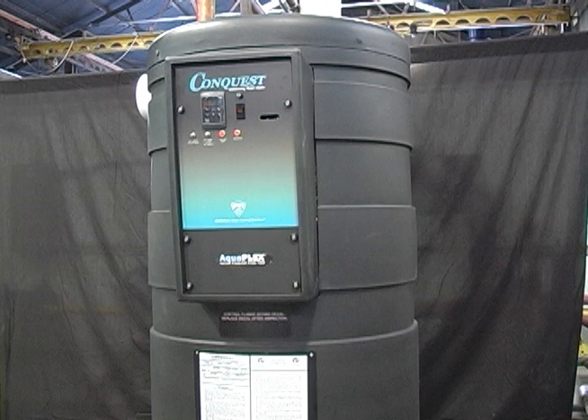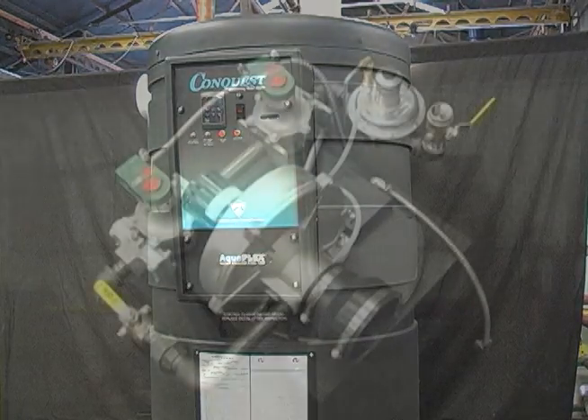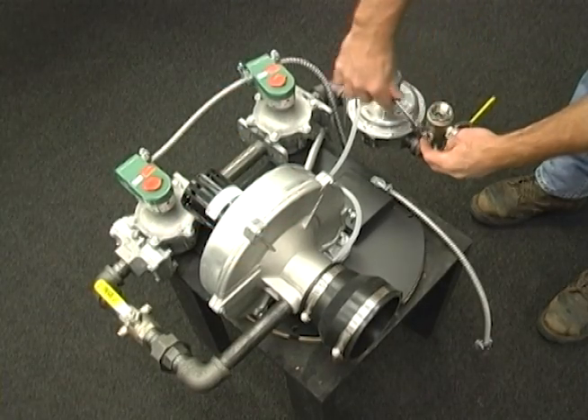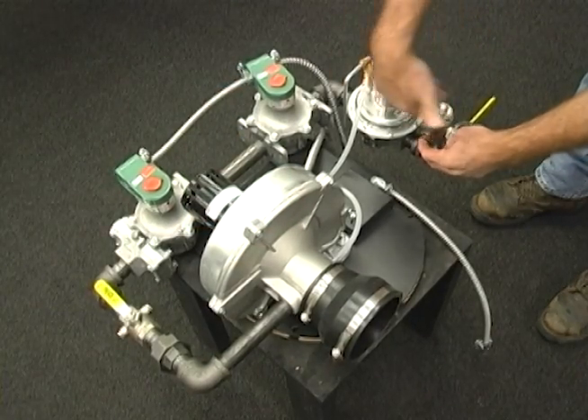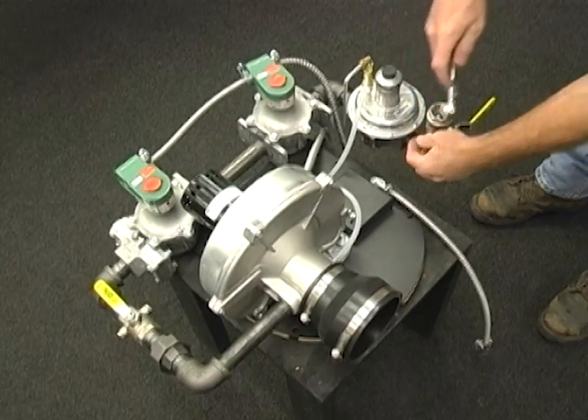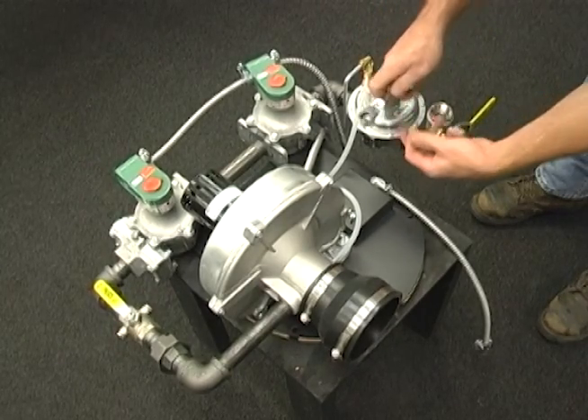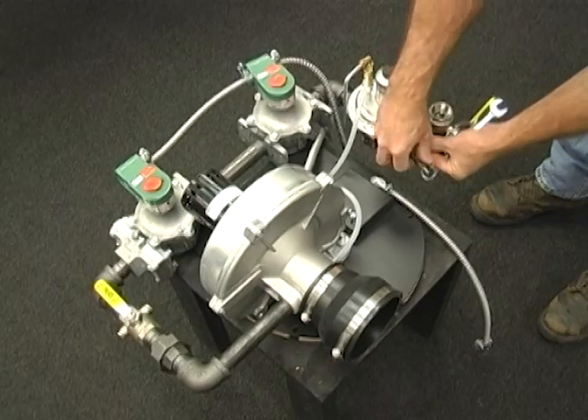The next step is to confirm that adequate gas pressure is supplied to the water heater. For ease of viewing, we will demonstrate these procedures on bench models of the gas trains, as well as on the heater itself. Begin by closing the manual gas shutoff valve at the beginning of the gas train, upstream of the gas train components. Attach a manometer tube to the test port on the manual shutoff valve.